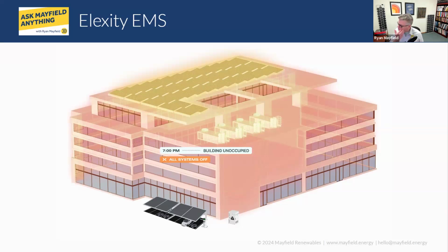We have to be really flexible. When you're getting into a building, it's a swamp, and you need to make very building-specific decisions. But essentially, for batteries, it's typically Modbus over TCP. The EMS creates a private network—we don't want to have a Modbus interface available on a publicly accessible network, even within the building. It needs to be isolated and secured.